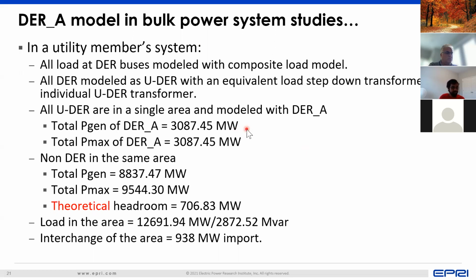This is not at a single substation. This is a bunch of substations in a given area in the system. You can consider the area to be a few counties in a state, which can sometimes be an entire state also, depending upon how big a transmission system we are considering, but consider it to be around 3,000 megawatts. And we have around 700 megawatts of headroom available in this area in terms of generation. And the goal is to study what will happen if this area disconnects from the rest of the system.